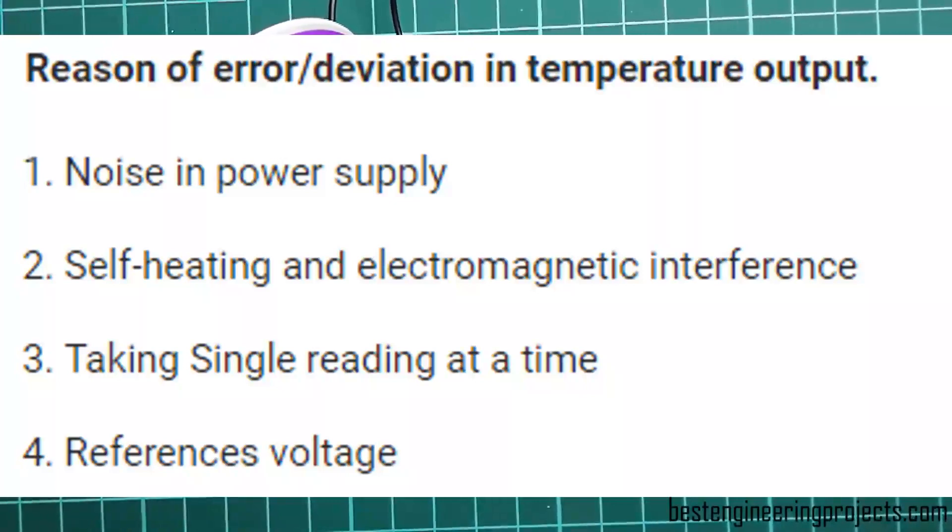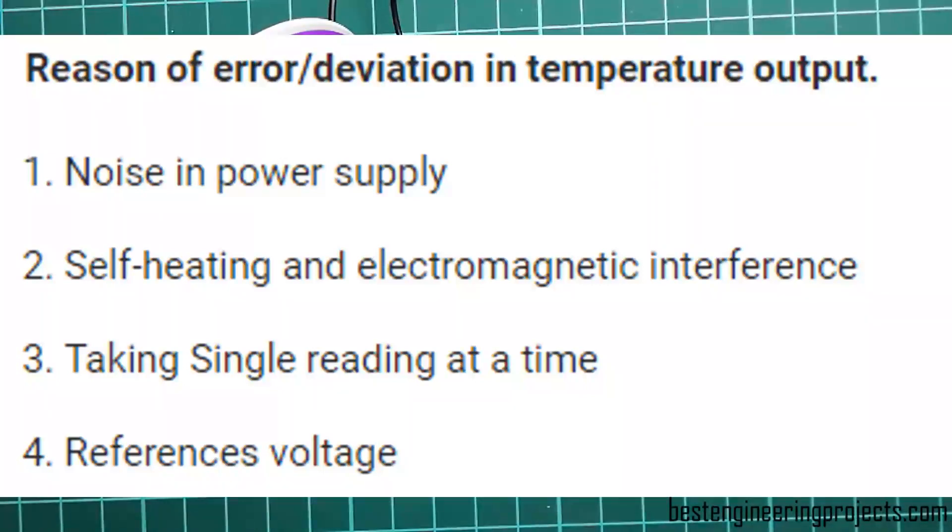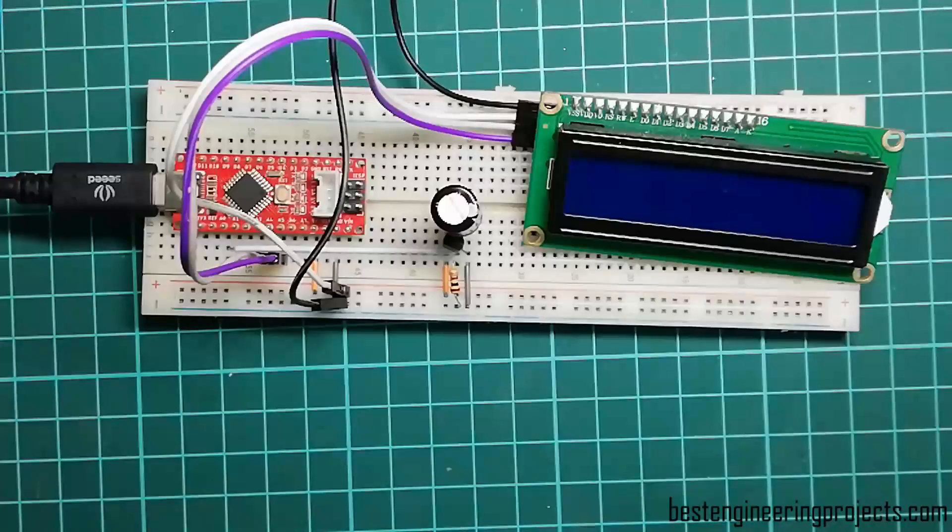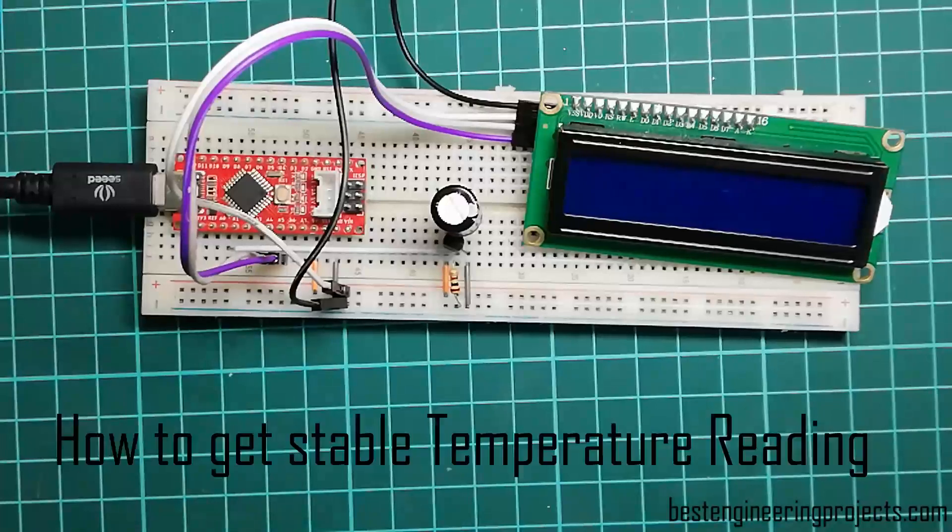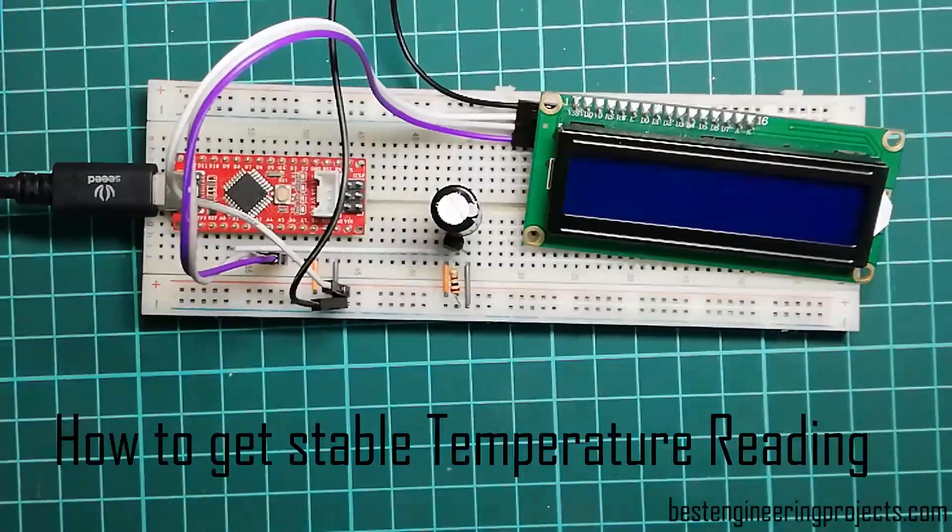Now let's see the reasons for deviation in temperature output. They are: 1) noise in power supply, 2) self-heating and electromagnetic interference, 3) taking single reading at a time, and 4) reference voltage. Now let's see the solution to every issue. First, let's see how to get stable temperature readings.